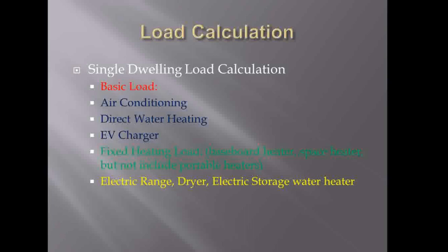For a single dwelling, the load calculation includes several parts. The first, shown in red, is the basic load. The second, third, and fourth are air conditioning, direct water heating, and the EV charger. After that is the fixed heating load, like a baseboard heater or space heater. The last is the electric range, dryer, and hot water tank — we call it the additional load.